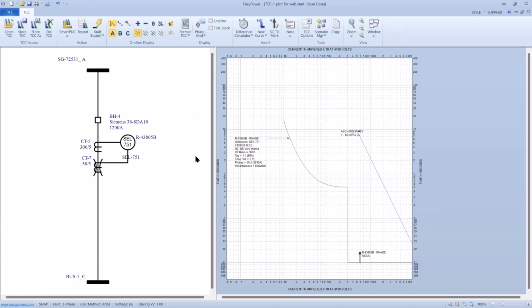Yeah, so Roger's asking, is the trip time on the one line excluding the breaker? The answer is yes. The plot on the TCC, what the sequence of events shows and what the one line shows is the response that we've generated with the TCC of the relay. So it ignores what the breaker opening time is.